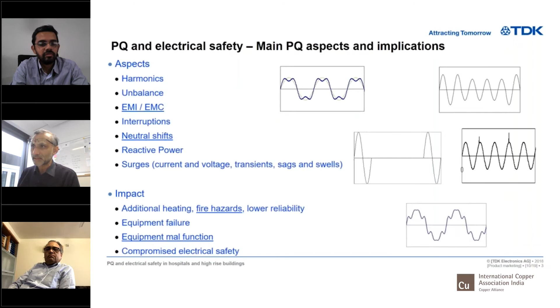Whenever you have a power quality problem, you get faster aging because of heating—we know there's an 8-degree or 10-degree rule, and insulation ages much faster. So a transformer designed for, say, 40 years can live only for 20 years. Mr. Mehta was talking about high-rise buildings living for 80, 90, 100 years.